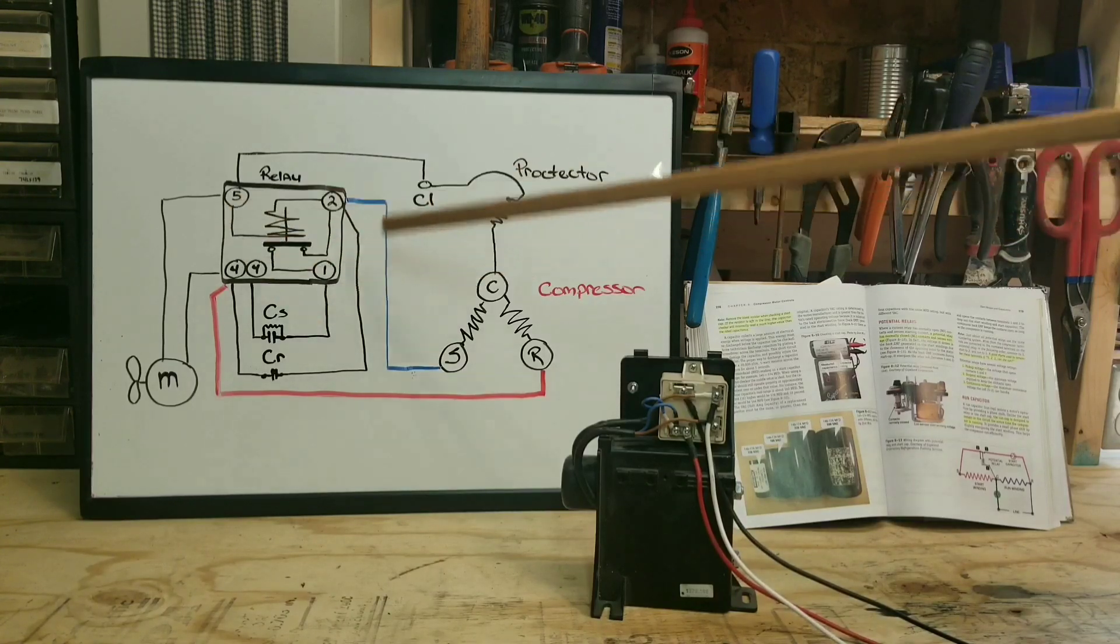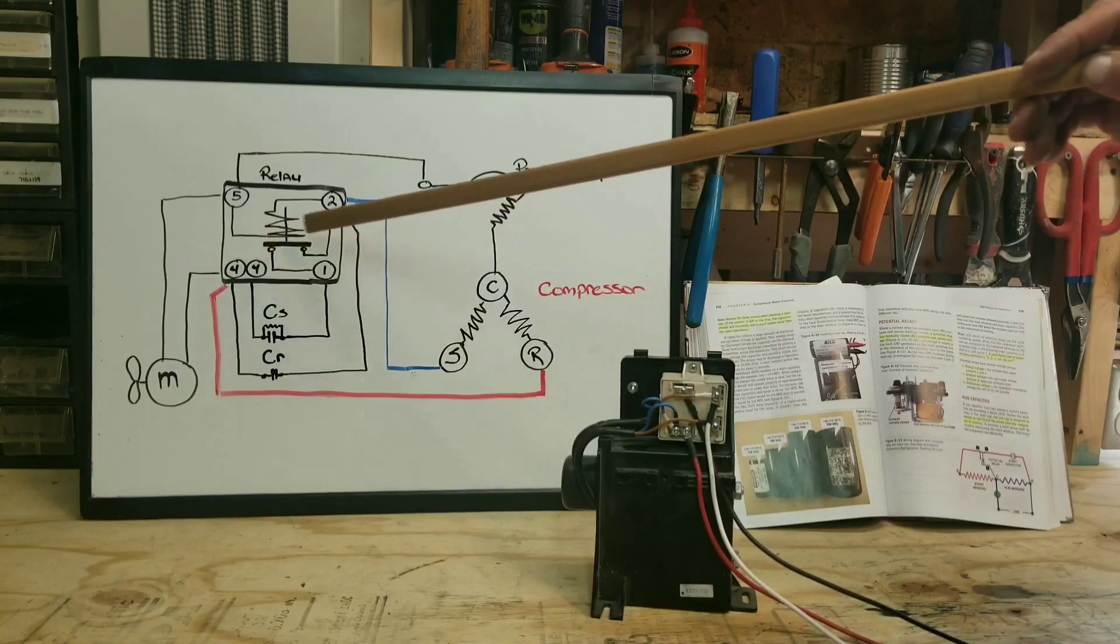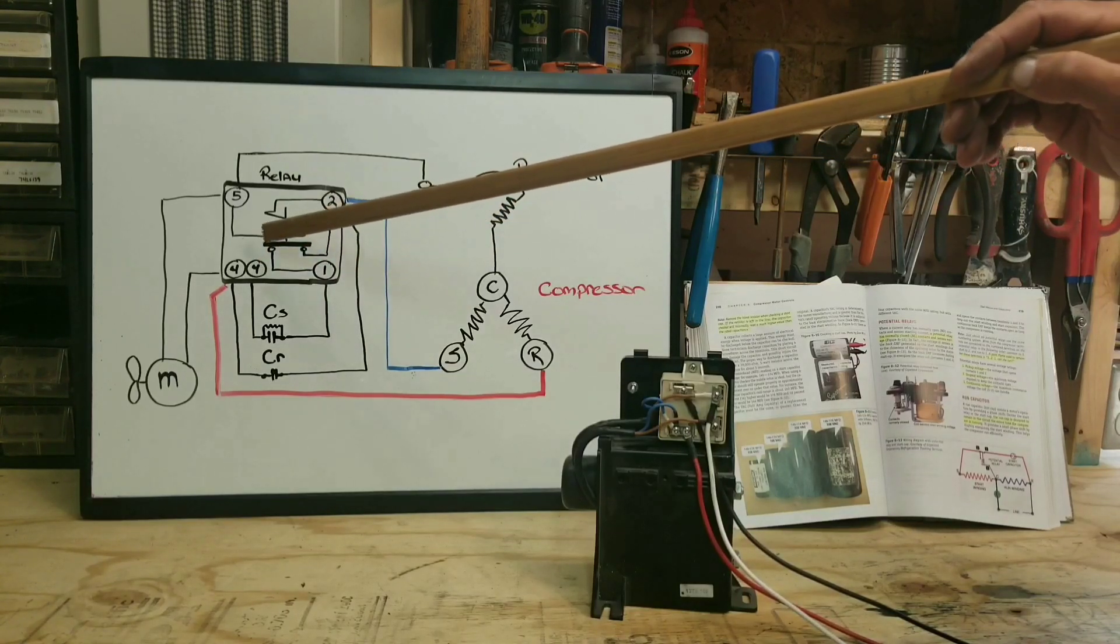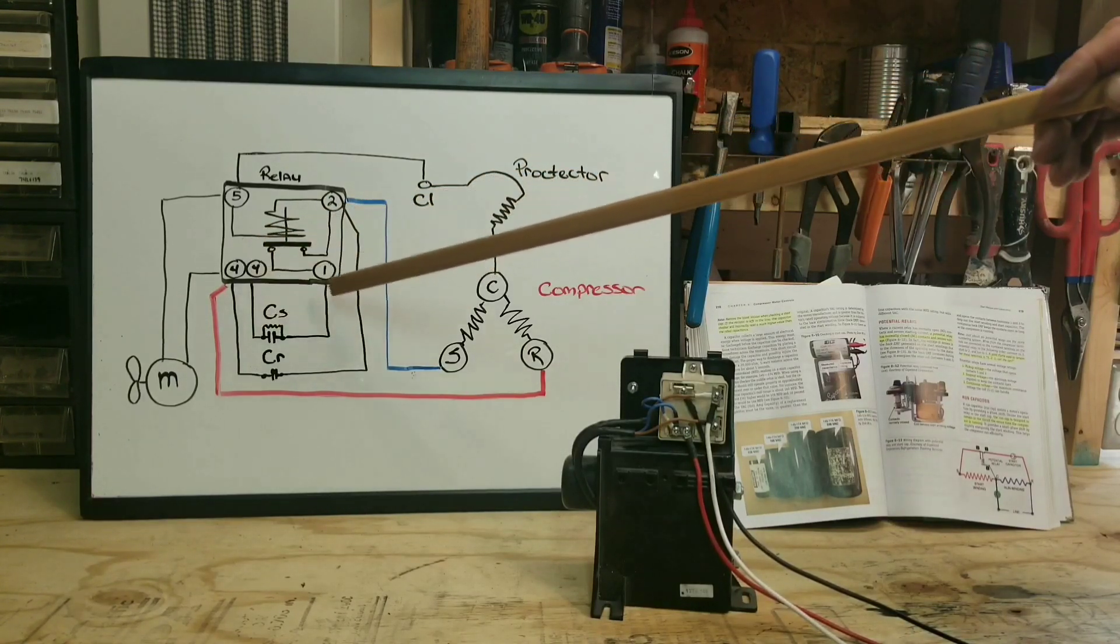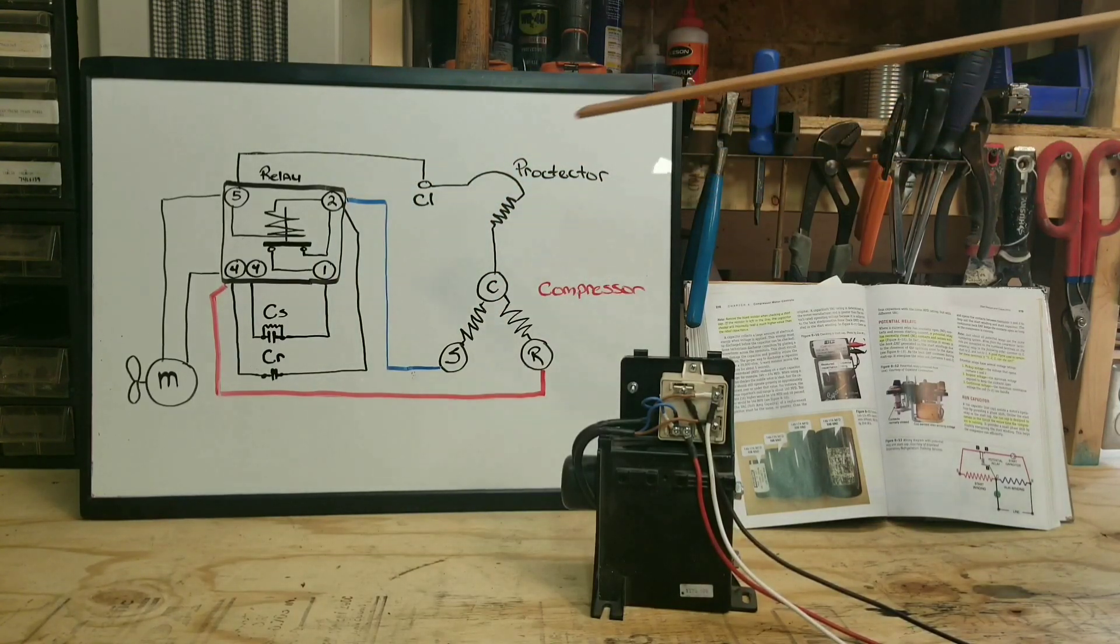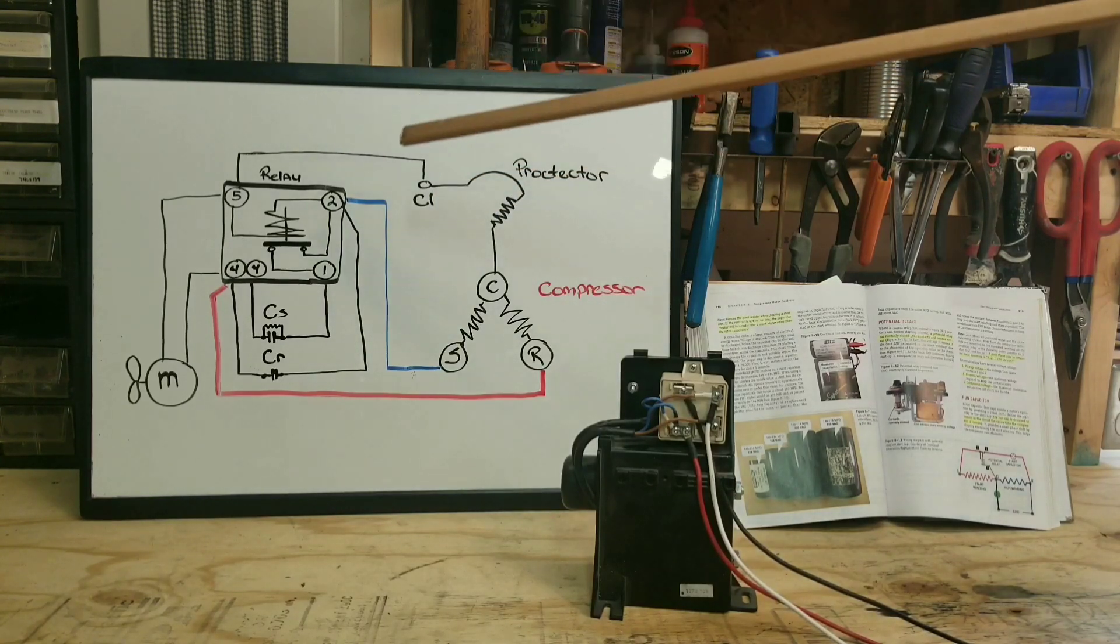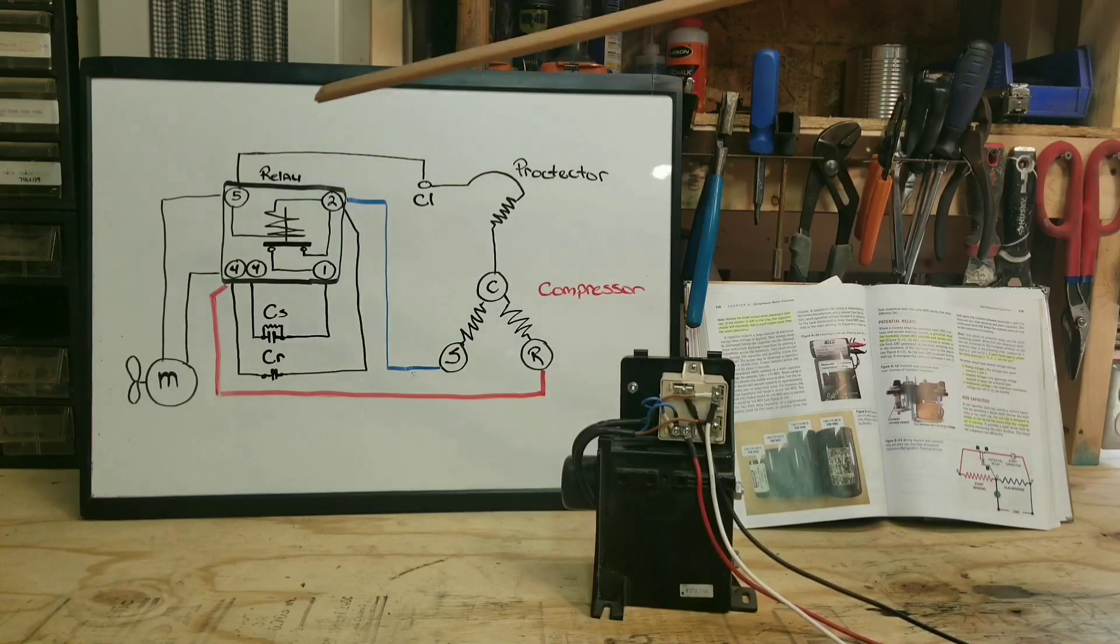And what happens is we get a call for cool, condensing unit kicks on. This is closed to begin with, so our start capacitor kicks in, helps turn our compressor over. We start running.